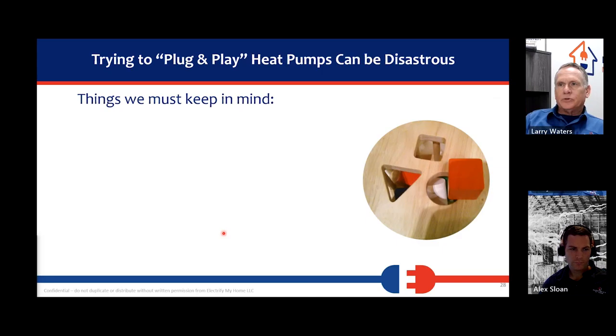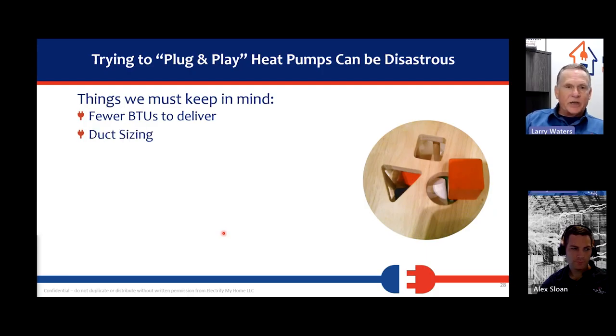Okay. So trying to plug and play heat pumps, trying to pull a gas electric system out and plug and play a heat pump, it can cause major problems. And companies out there are seeing this now. They're seeing customers complain about high bills, noisy systems, it's blowing cold air on me. It's not what you explained it was going to be. It's not saving me money. There's a lot of challenges in installing heat pumps properly. So good thing y'all came today. We have a lot fewer BTUs to deliver with a heat pump. We need to make sure duct sizing is right, and putting a new reduced capacity heat pump system on old ductwork that we're not checking and verifying has the right capacity is problematic.